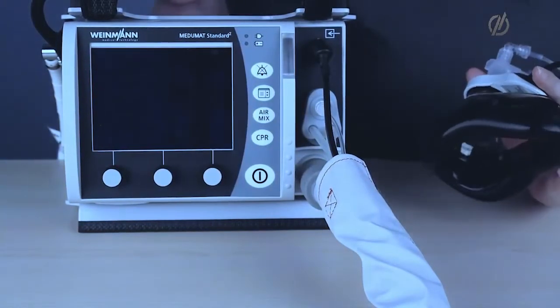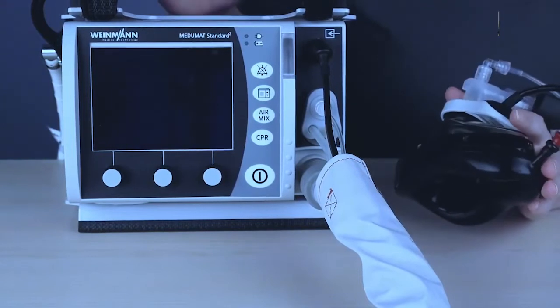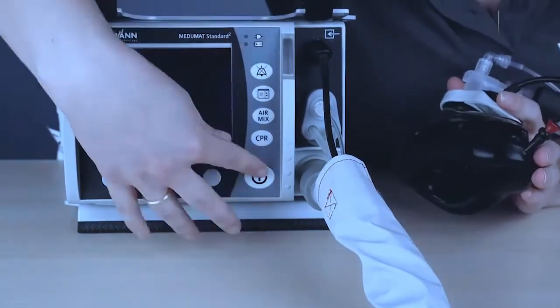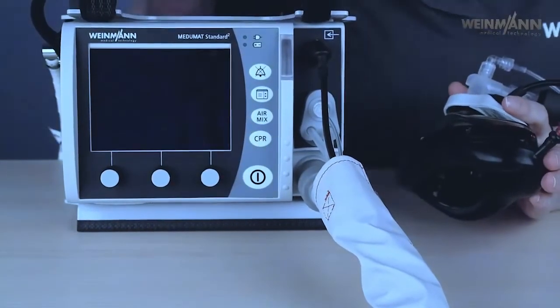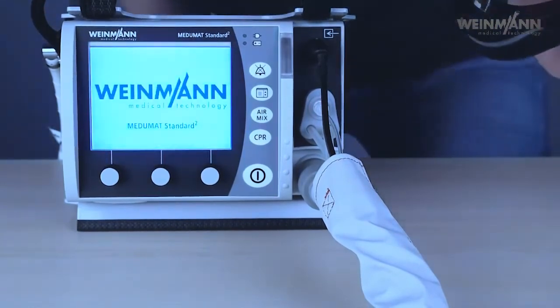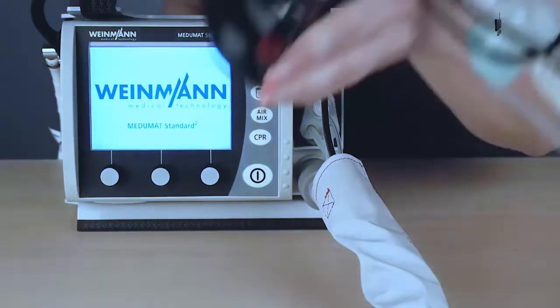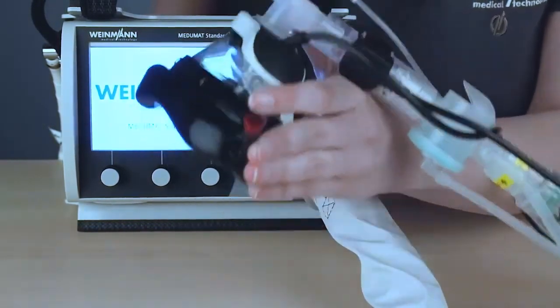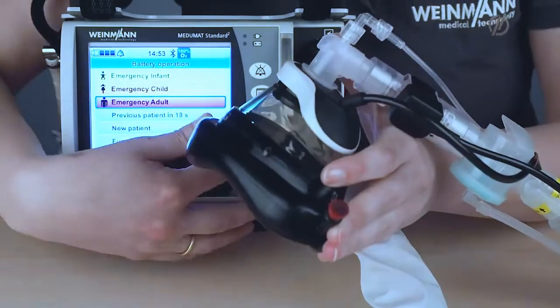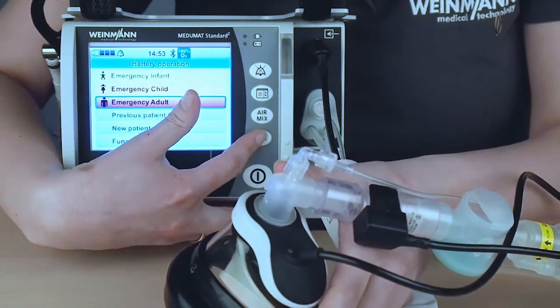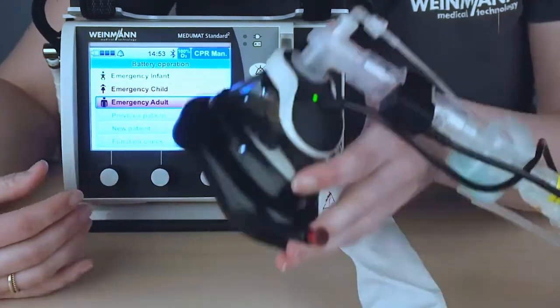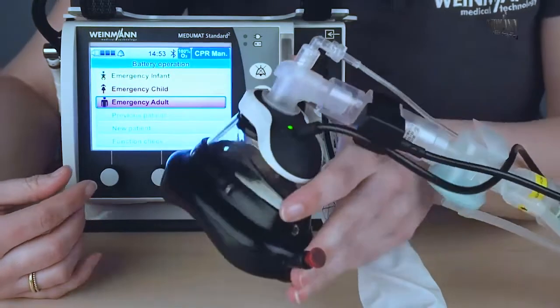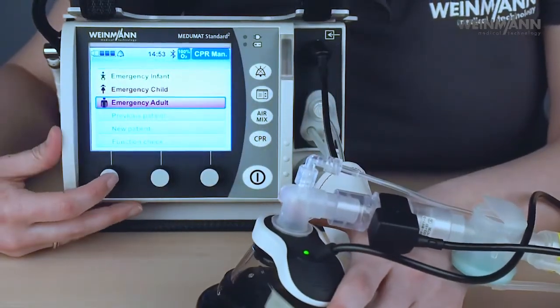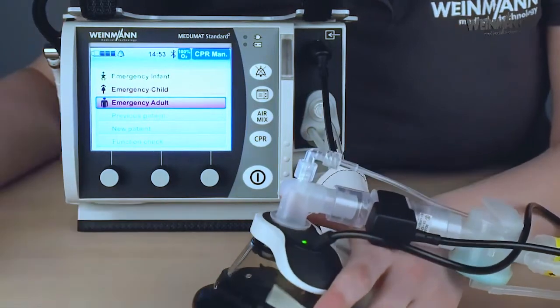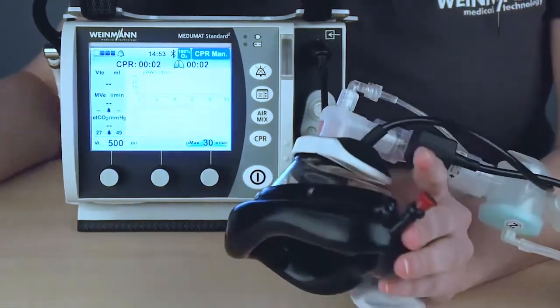Okay, so now I would like to show you the special function of this device. This is CPR. Turning on the device again and waiting for it to start up, I have connected my ventilation mask to the hose system, because this is the first part of the CPR mode. I will go now to CPR. Obviously, you can also choose the CPR mode from a standard ventilation. I will go also to emergency adult, and I'm automatically in my CPR mode.